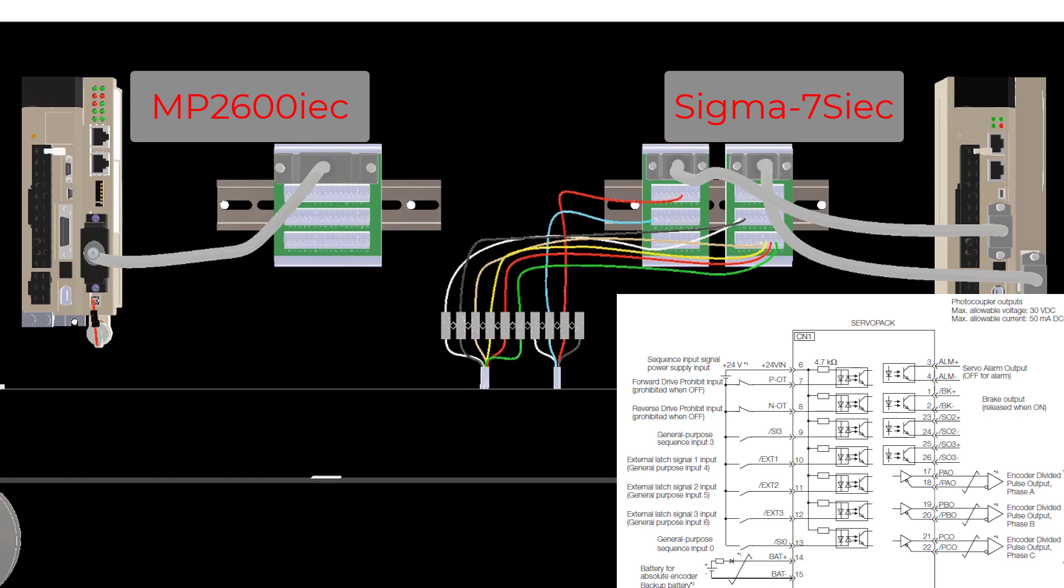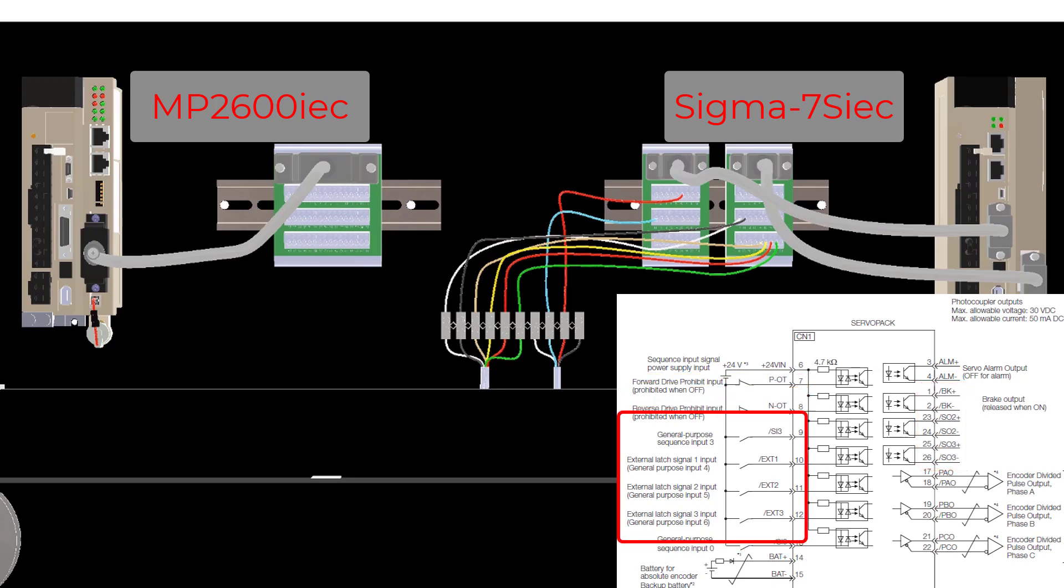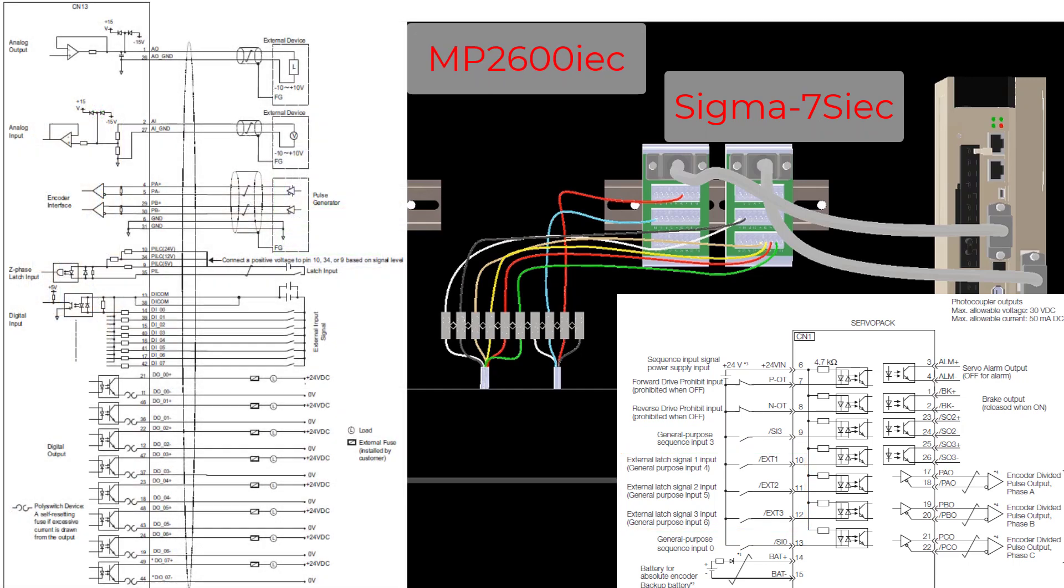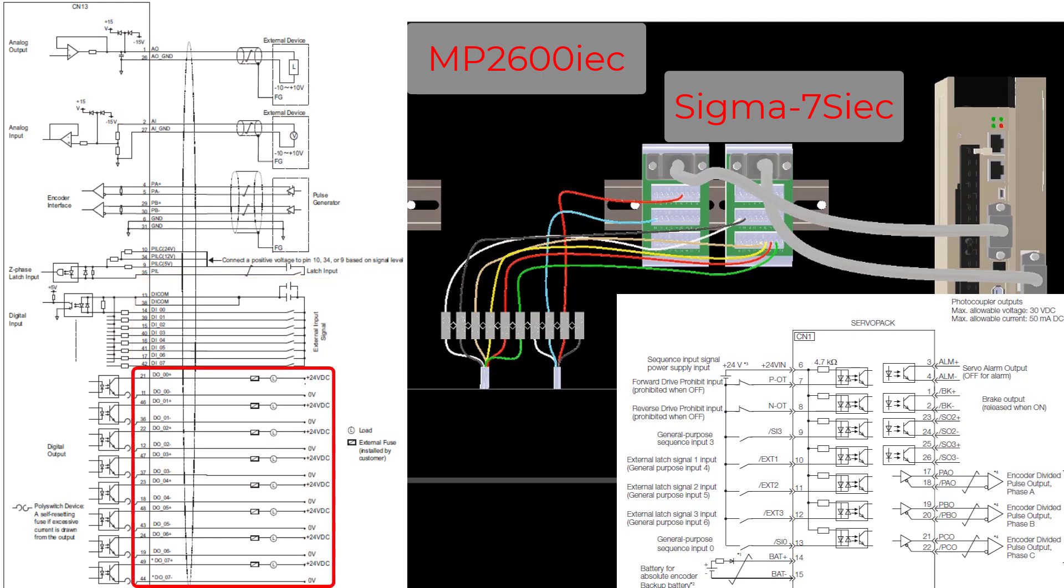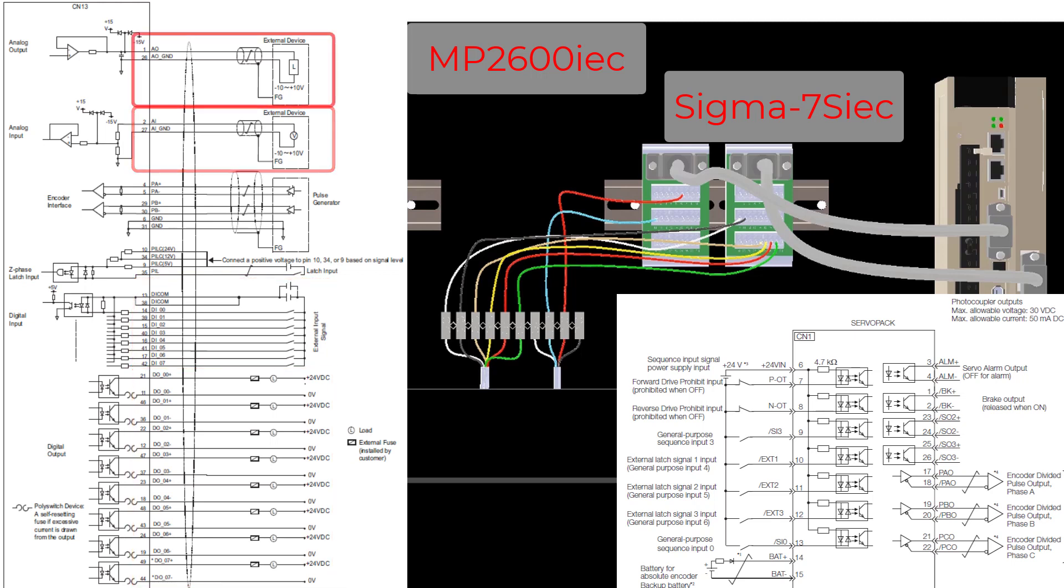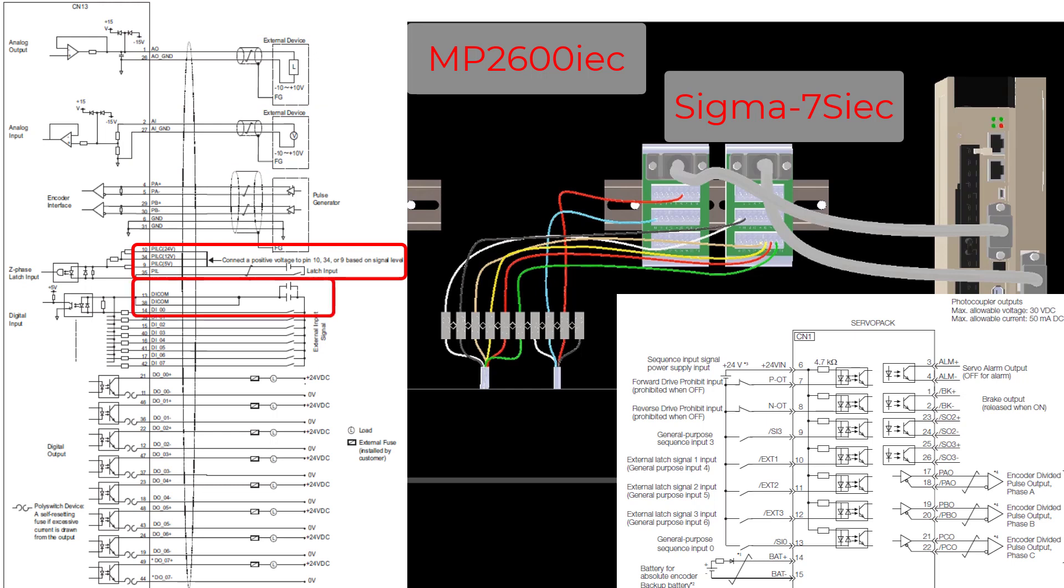The Sigma-7S IEC only supports 7 digital inputs and 3 digital outputs. 3 of the digital inputs can be used for high speed latch inputs. The MP2600 IEC controller supports 8 digital inputs, 8 digital outputs, 1 analog input, 1 analog output, and a Z-phase latch input. The Z-phase latch input and 1 digital input can be used as a high speed latch.